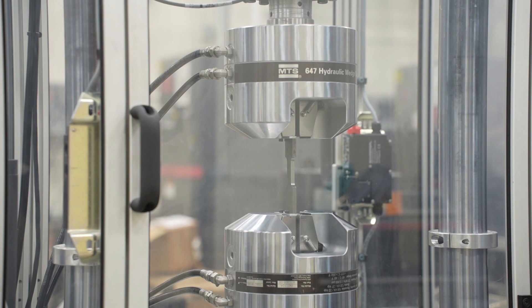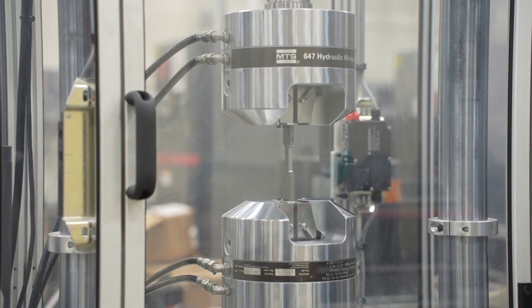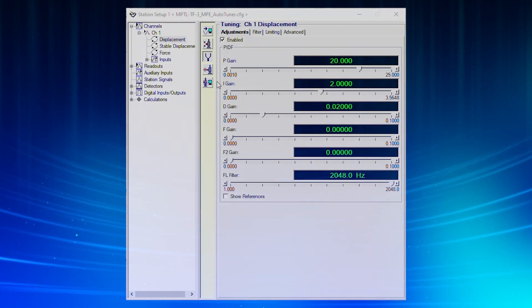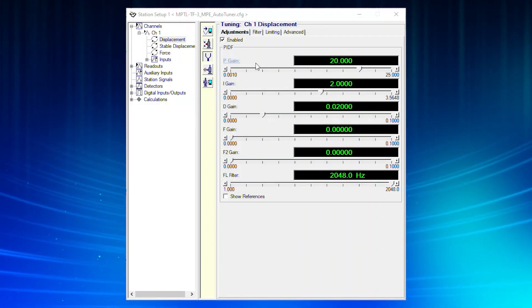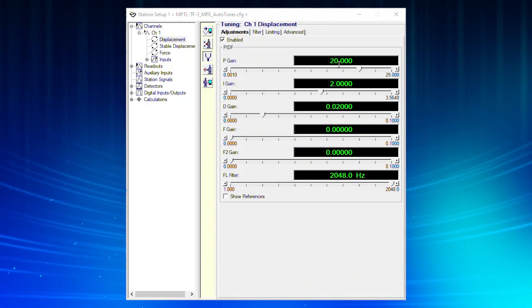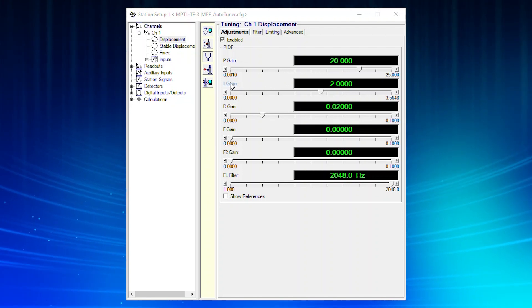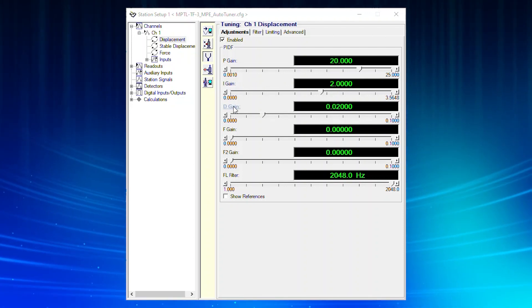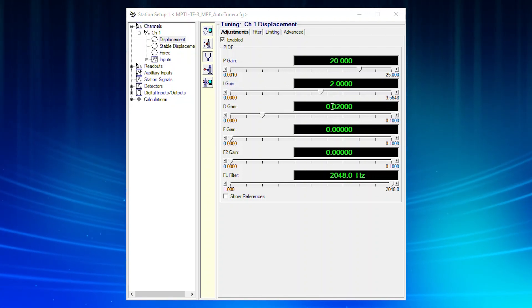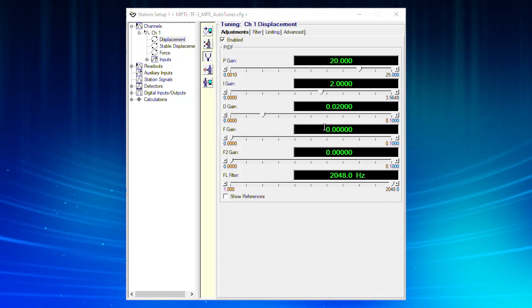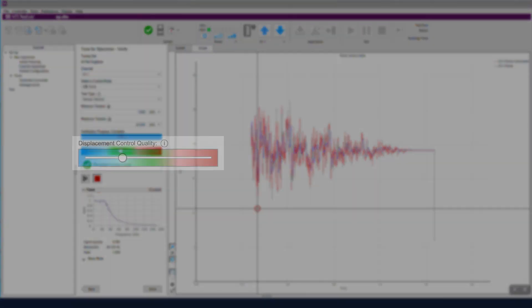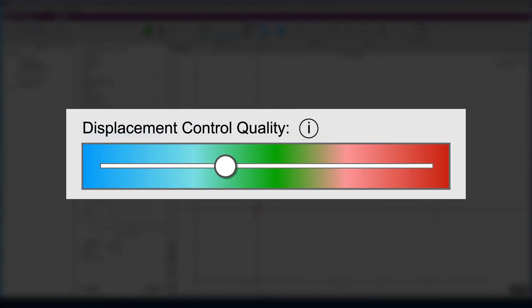So to improve system performance and attain more accurate results, test operators must adjust PID tuning values which can be cumbersome and confusing to do, especially for those new to testing. That's why MTS added a visually intuitive auto-tuning feature.